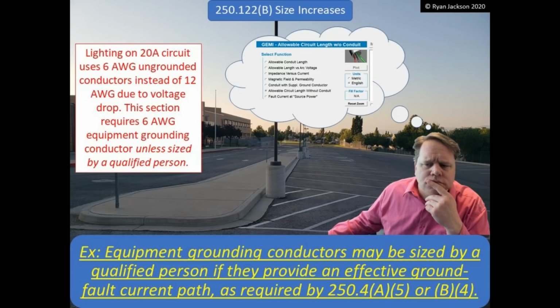All right, so there you go. You can go ahead and use a software like the GEMI software. And of course, there's other, more elaborate softwares out there, I'm sure, but this is a nice, easy, free one. And you can use it to size the equipment grounding conductor when you're increasing in size for voltage drop or other reasons other than temperature correction or adjustment factors. So a rather surprising allowance, but I think it's a good allowance. Again, I'm not saying that it's perfect, but I think it's better than anything that we've had so far. It does give us some leeway when the general requirements don't make sense at all. So there you have it. I hope this helped you out with 250.122(B). Like I said, it is kind of a tricky topic and a trippy topic for that matter.